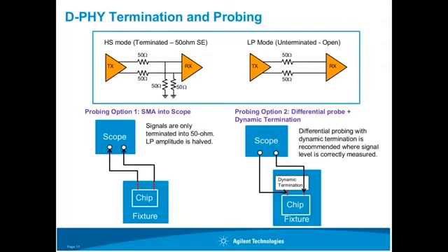Okay, thank you. The next question, is the precision probe feature supported on the electrical test packages? Yeah, the precision probe is definitely supported in the automated software that we provide. So we understand that you have a need to make better measurements, right? Not only by hand, but also with the automation tool. So we do incorporate that feature and capability into the application for better measurement accuracy. Yes, we do.